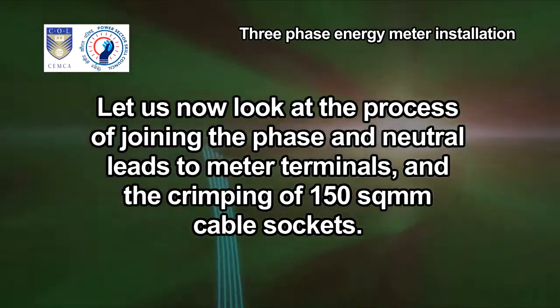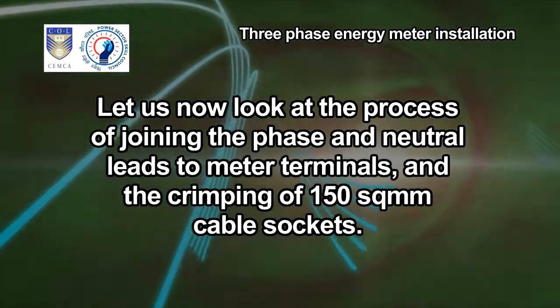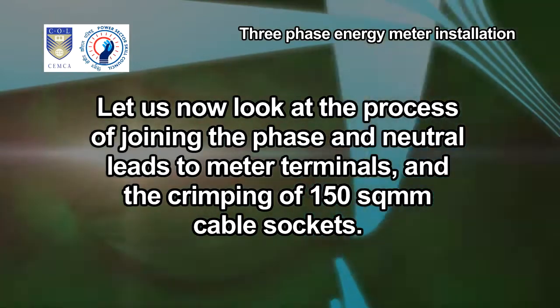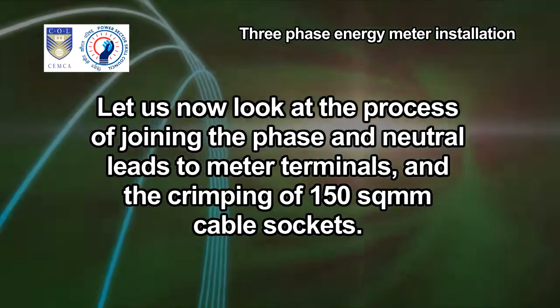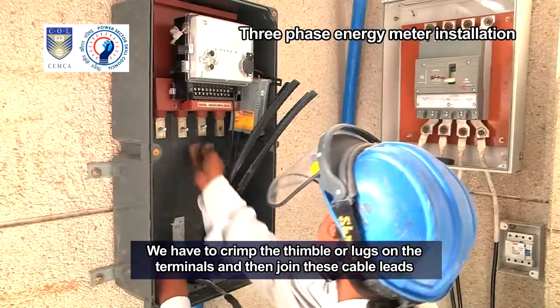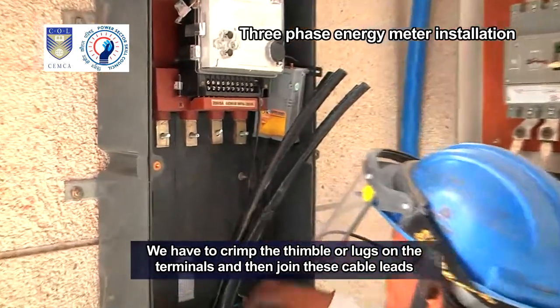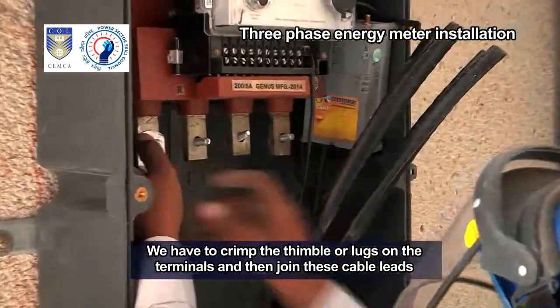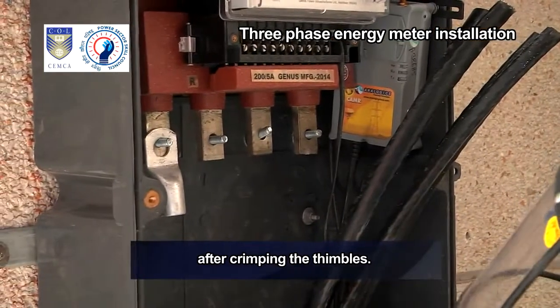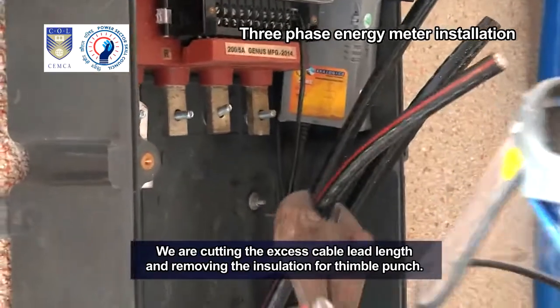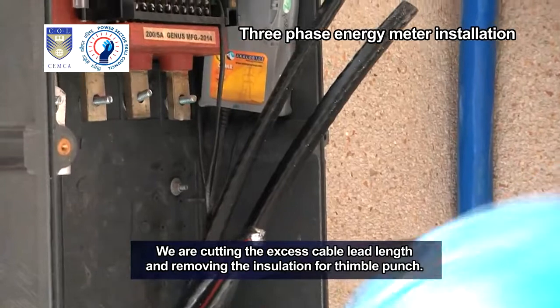Let us now look at the process of joining the phase and neutral leads to meter terminals and the crimping of 150 square mm cable sockets. We have to crimp the thimble or lugs on the terminals and then join these cable leads after crimping the thimbles. We are cutting the excess cable lead length and removing the insulation for thimble punch.